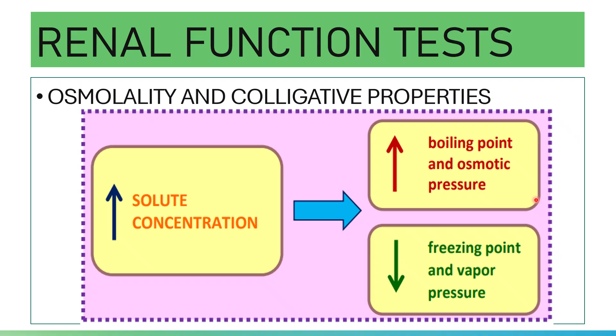Changes in these colligative properties are proportional to osmolality. Accordingly, changes in the colligative properties of a solution are somewhat proportional to the osmolality of the solution. In short, your osmolality measures the number of dissolved particles in a solution. And yes, for us in the laboratory, we determine osmolality by observing the changes in the colligative properties, especially the freezing point depression, which is actually employed in most of your osmometers. Measurement of your osmolality is performed for a more accurate evaluation of the renal concentrating ability. Osmolality is more accurate than specific gravity.